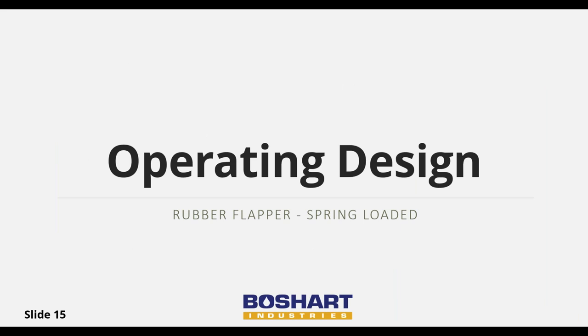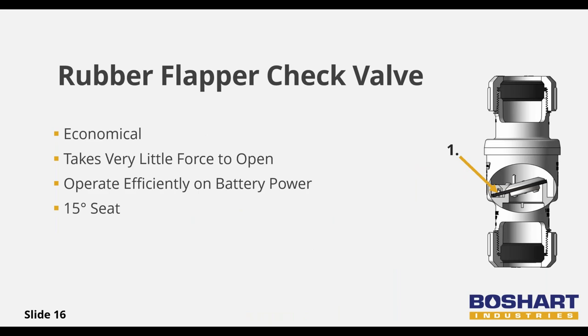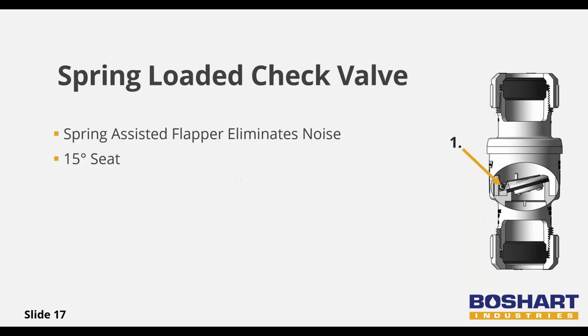Boshart offers two operating designs of swing check valve: the gravity-type flapper and a spring-assisted flapper design. The gravity design operates by gravity — the pump forces water through, but gravity and the weight of the water push back to close it. Benefits include being more economical and requiring very little force to open, so it can run on a battery-powered backup pump in emergencies. Both designs feature 15-degree seats, which reduce water hammer and flapper noise by reducing the time it takes for the flapper to close.